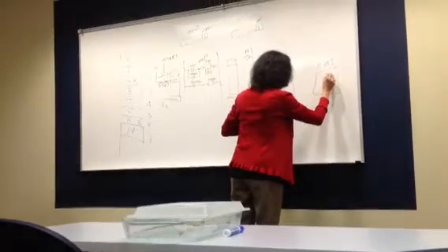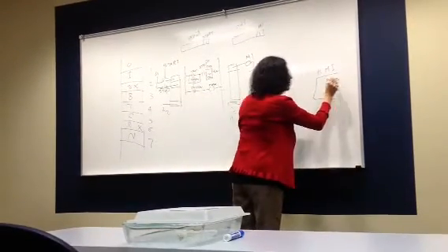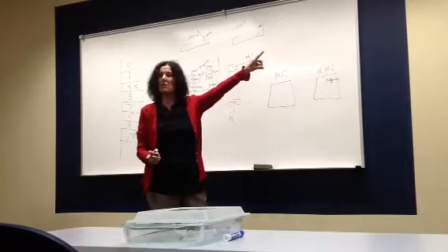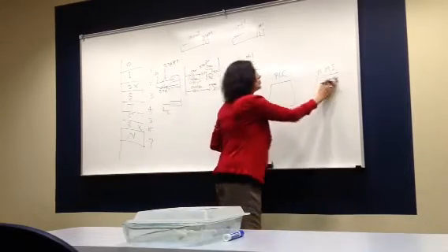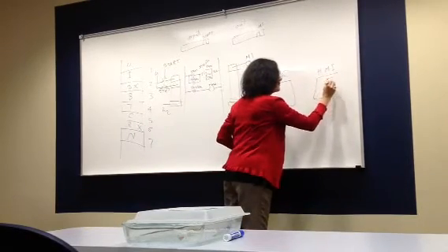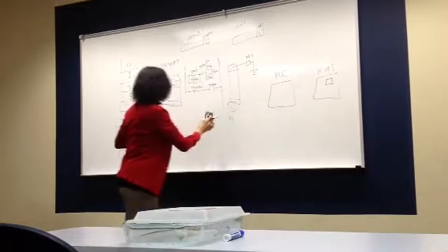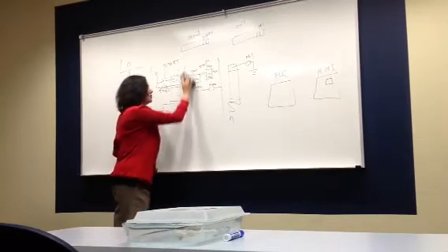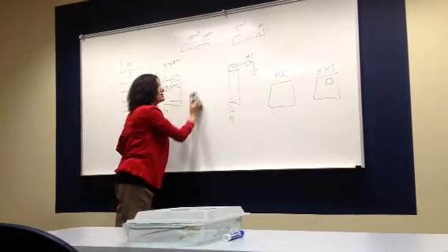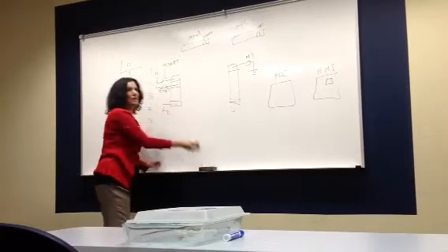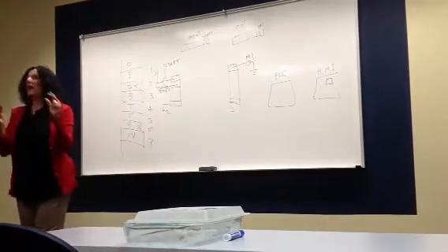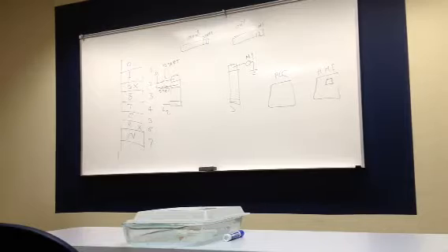Color, orange, till someone goes and fixes the motor, and then it goes back to green. So I want to send the motor output, assuming that I already sent it. I'm not going to do the logic for that. I'm going to send the motor output, and if the motor output is true and I don't receive the input in 5 seconds, send me an alarm.